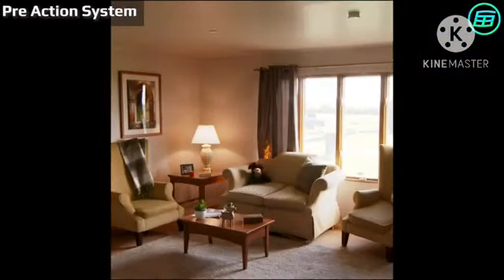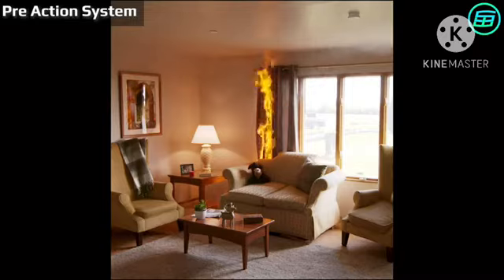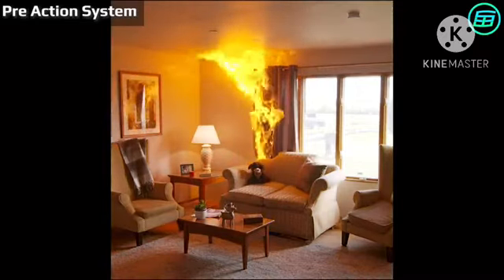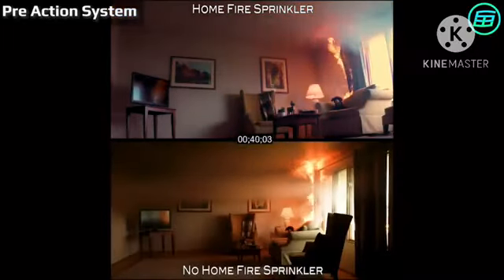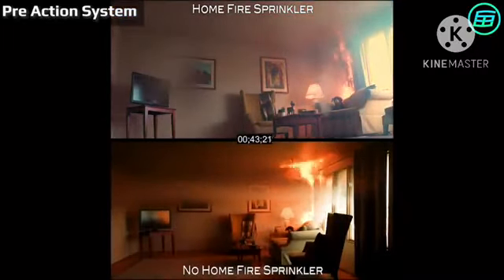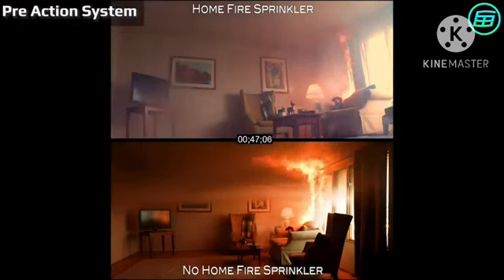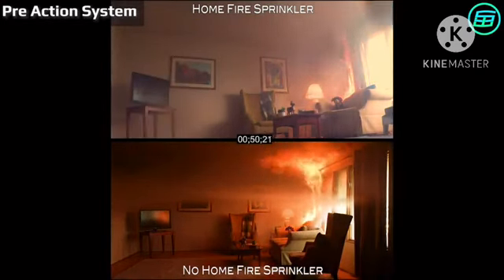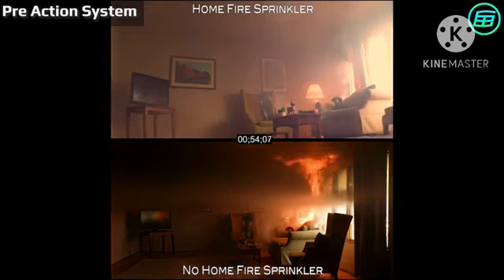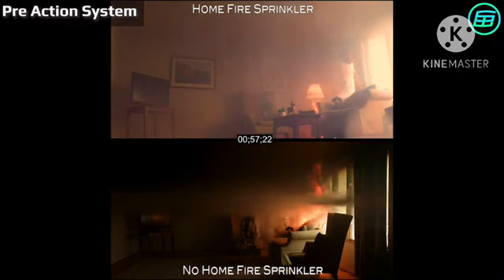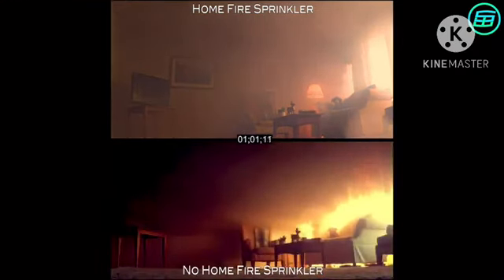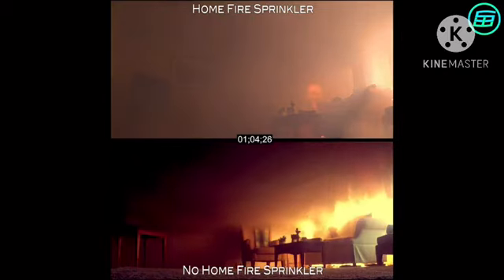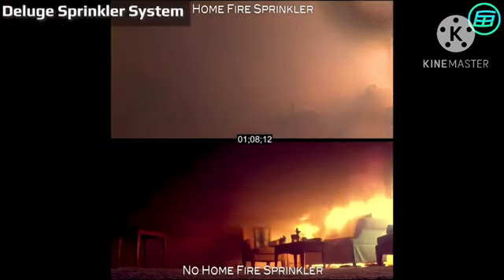Pre-action systems are a kind of dry pipe sprinkler system that require two activation steps. When heat or smoke is detected, the pre-action valve opens and allows water into the pipes. Then, the sprinkler heads can be individually activated to release water over the fire. This two-step process enables facilities to shut off the system in case of a false alarm, protecting assets from water damage. Pre-action systems are especially useful in places where accidental discharge could lead to irreparable damage, such as in museums, libraries and data centers. Another type of system is the deluge sprinkler system, which also uses dry pipe technology.